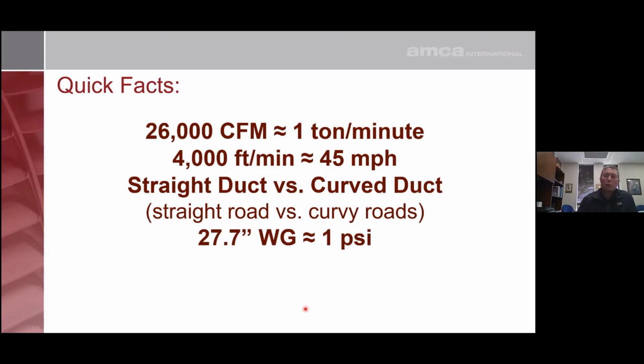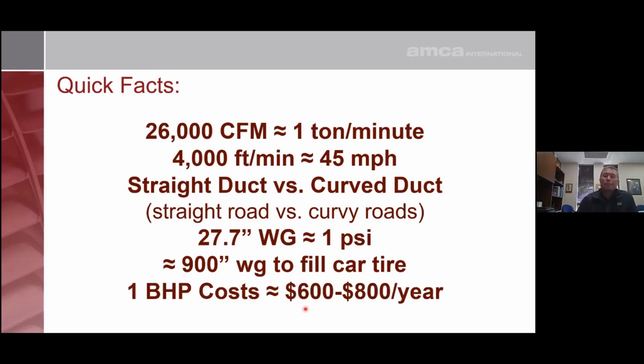As I mentioned, 27.7 inches of water equals 1 PSI, so inches of water is a relatively small number. It takes about 900 inches of water to fill up a car tire. And for estimating purposes, and this changes widely depending on where you live and your energy costs, I usually figure that for a fan running 24/7, 1 brake horsepower is roughly $600 a year.